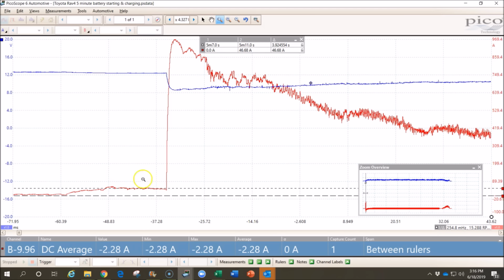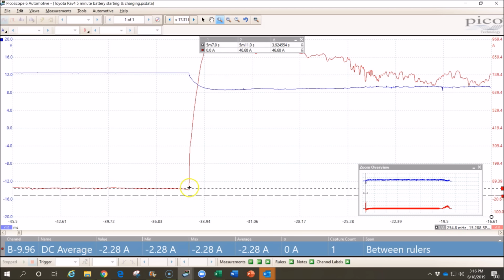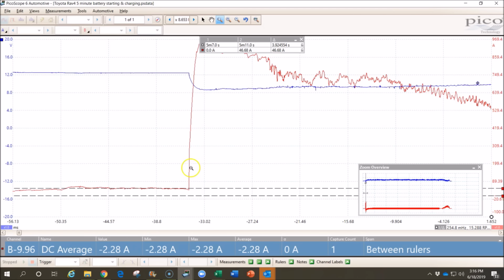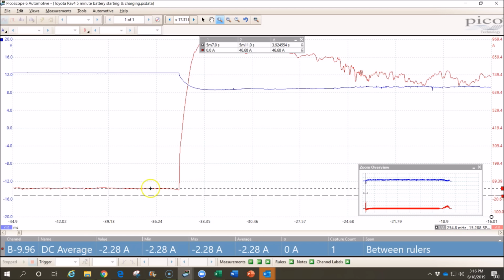When we come to this point, we want to zoom in and look at this line. So this is a very crisp line. When the solenoid contacts engaged, they engaged once. Often what you'll see is they engage once and then disengage and engage twice, and that represents bouncing or arcing solenoid contacts. So you can kind of determine the health of the solenoid right here.